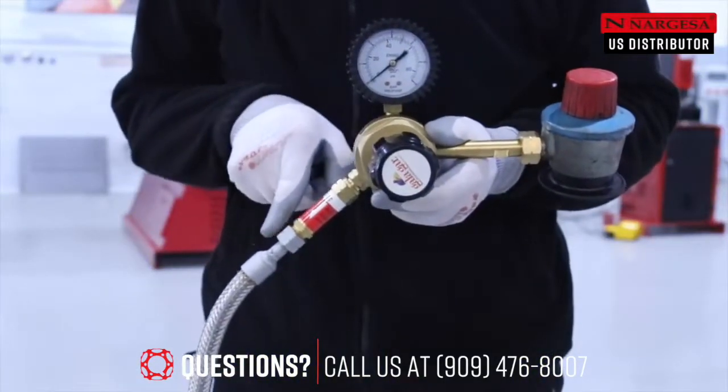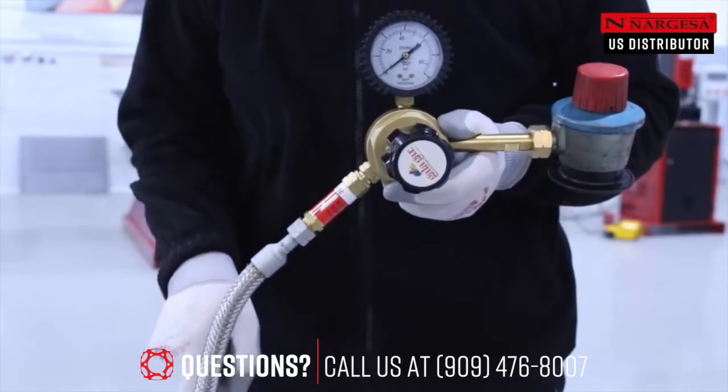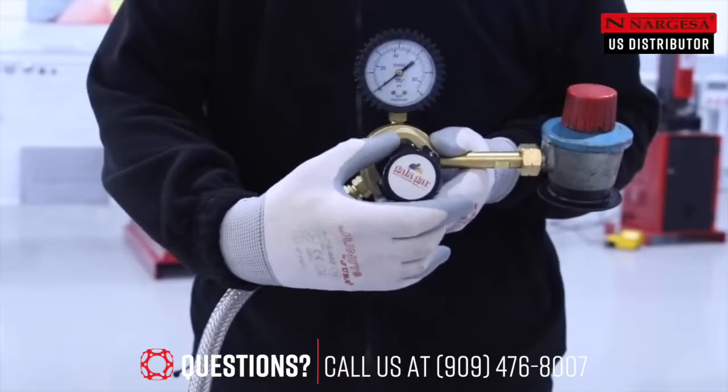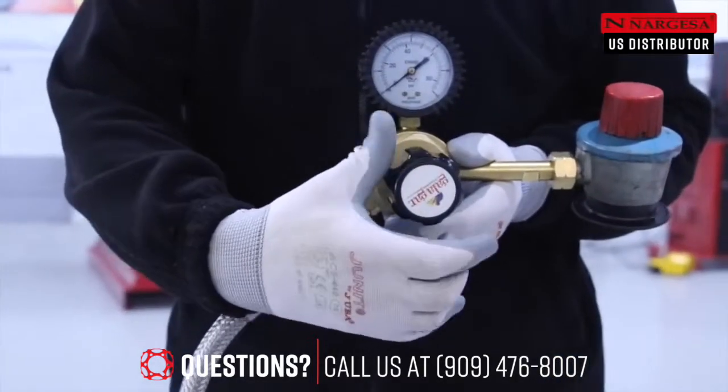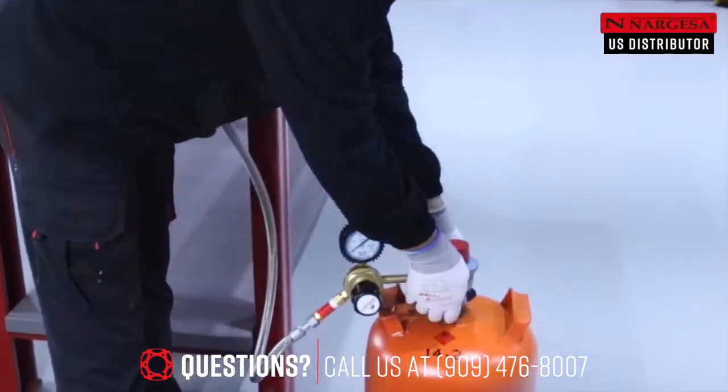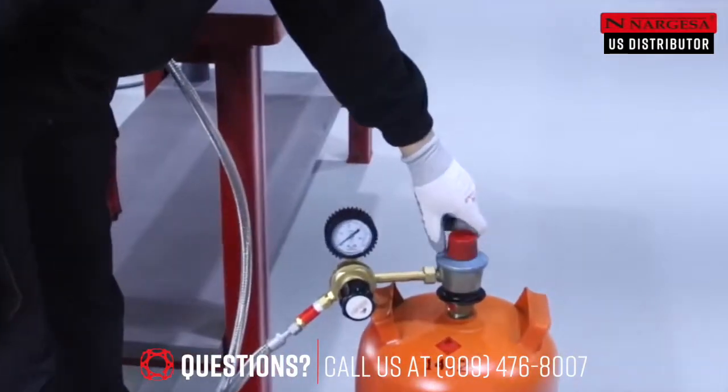A safety anti-return valve regulates the direction of gas flow, preventing the flame from going back into the cylinder. The pressure regulator with built-in pressure gauge allows to adjust the gas pressure more accurately.